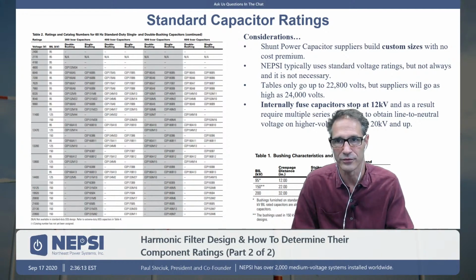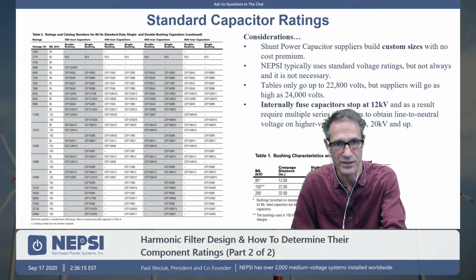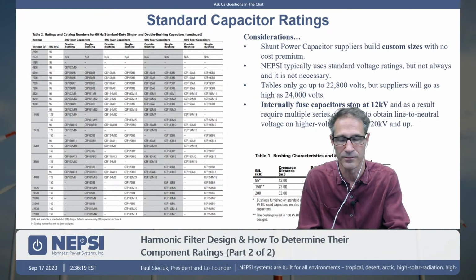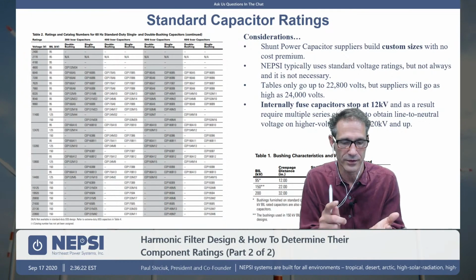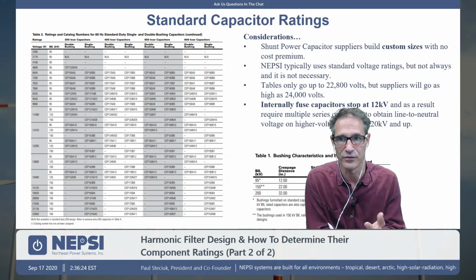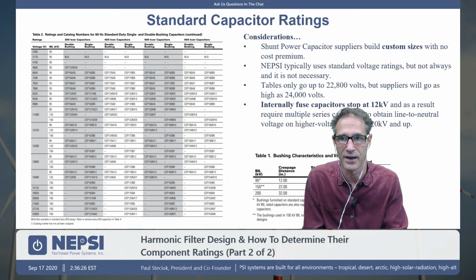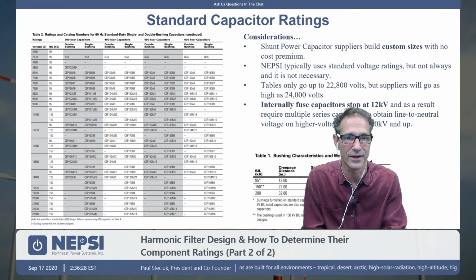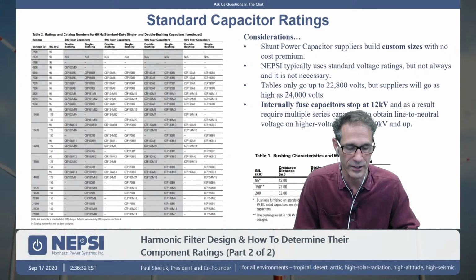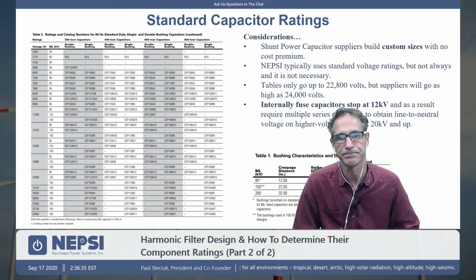So when you're into a standard design, you're into that manufacturer's standard design. You're not into a standard design that works across the board. So you have to choose a supplier, and you're choosing a kVAR. So if your filter design comes up with a non-standard voltage rating, non-standard kVAR rating, then ask for it. And you'll get it, and you're not really paying a premium for it.